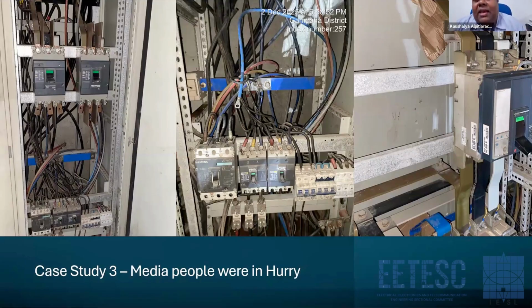They wanted a certificate to provide to the utility to switch on the panel. We politely rejected, and we explained the danger of doing it, and they promised that they were going to do a full recovery. After that, no hearing, and we are yet to be paid for our visits. If you switch this on, definitely you are going to face an arc flash and a disaster, because on top of this, the utility transformer was also placed.